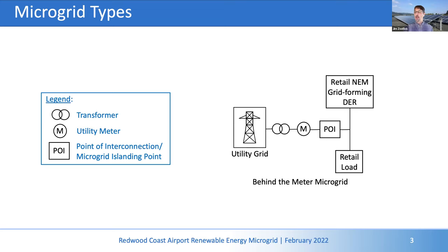It's possible for those resources to be grid forming and able to island load. When the point of interconnection or point of isolation, a microgrid islanding point switch opens, it isolates that generation and load from the main utility grid, and everything's behind the meter. That's a pretty simple system with not a lot of involvement from the utility, pretty much the same as interconnecting any DER. However, because the DER can be grid forming, there are additional safeties and checks the utility wants in place, because they don't want a grid forming generator operating in parallel with their distribution system.